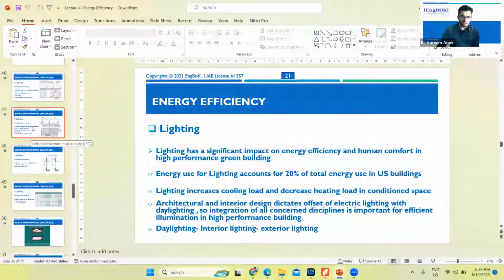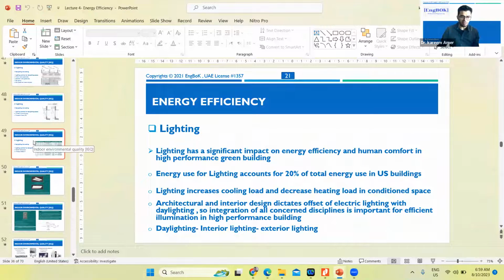We'll also cover calculation of daylighting and how to provide occupancy control or photo sensor control based on your type of control. We control wattage or time. We control time by scheduling or by occupancy. For example, if you have an office building and you know the employee schedule, you can schedule your building accordingly. This provides energy efficiency by reducing operating time, or you can reduce wattage by dimming or using efficient lighting like LED.